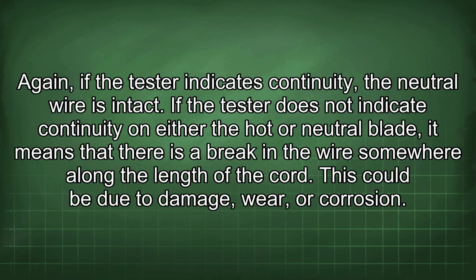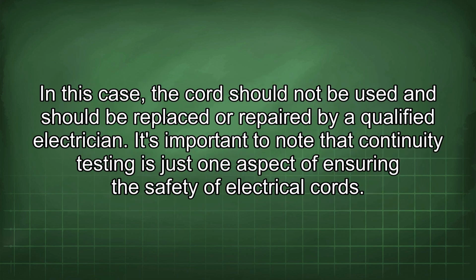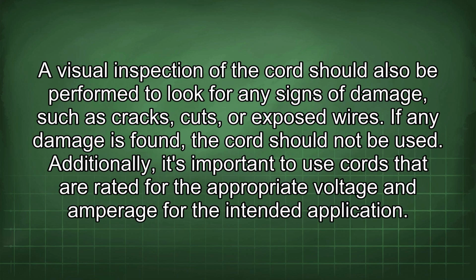If the tester does not indicate continuity on either the hot or neutral blade, it means that there is a break in the wire somewhere along the length of the cord. This could be due to damage, wear, or corrosion. In this case, the cord should not be used and should be replaced or repaired by a qualified electrician. It's important to note that continuity testing is just one aspect of ensuring the safety of electrical cords. A visual inspection of the cord should also be performed to look for any signs of damage, such as cracks, cuts, or exposed wires. If any damage is found, the cord should not be used.